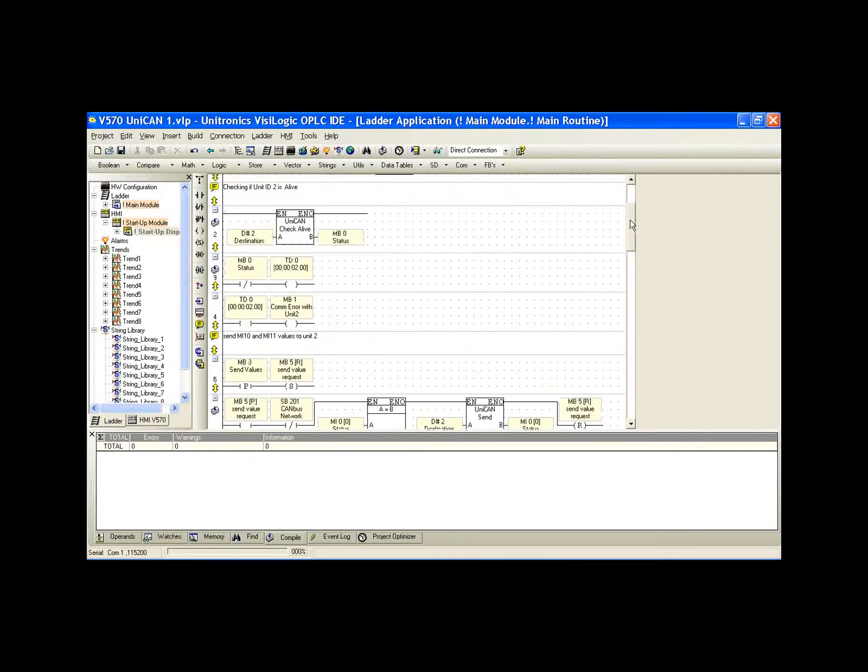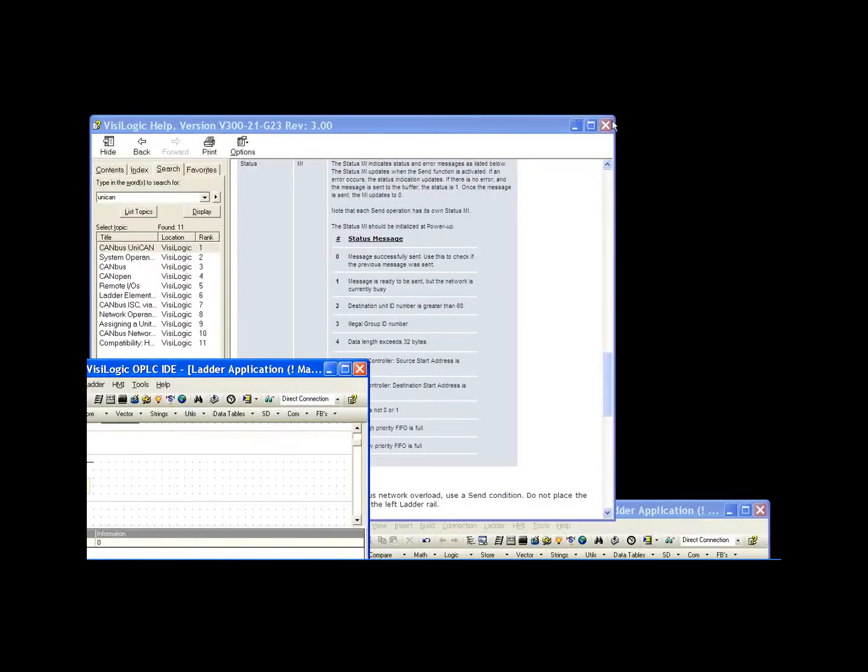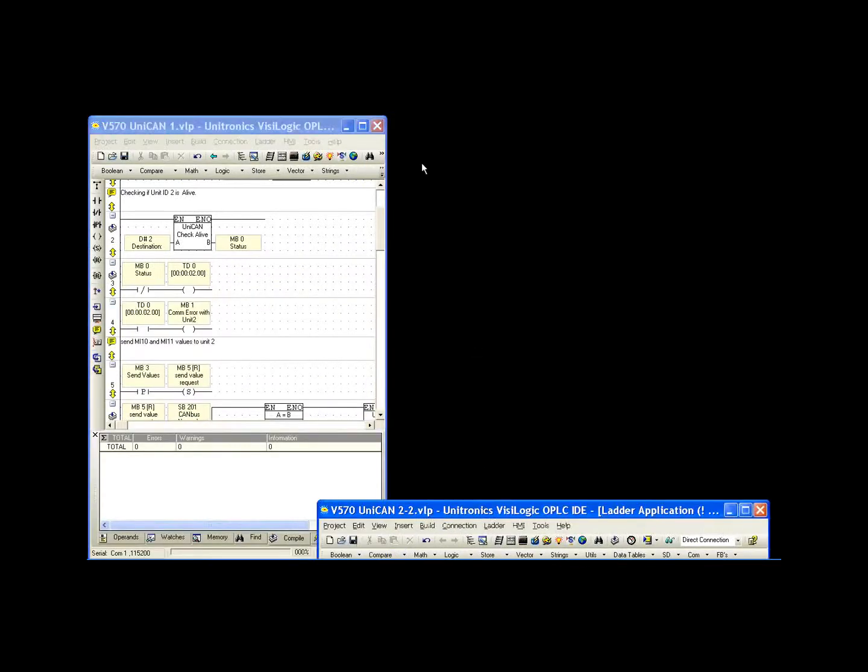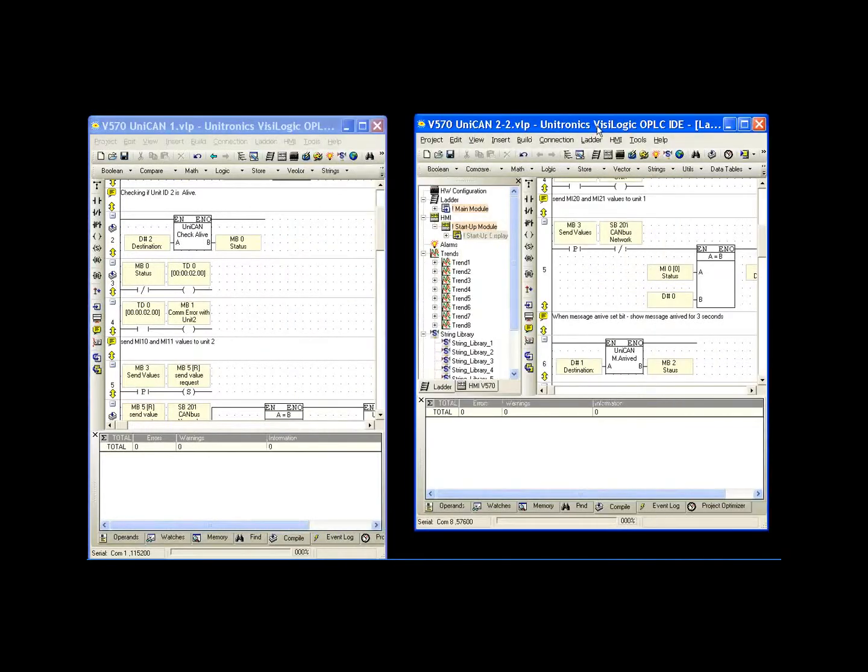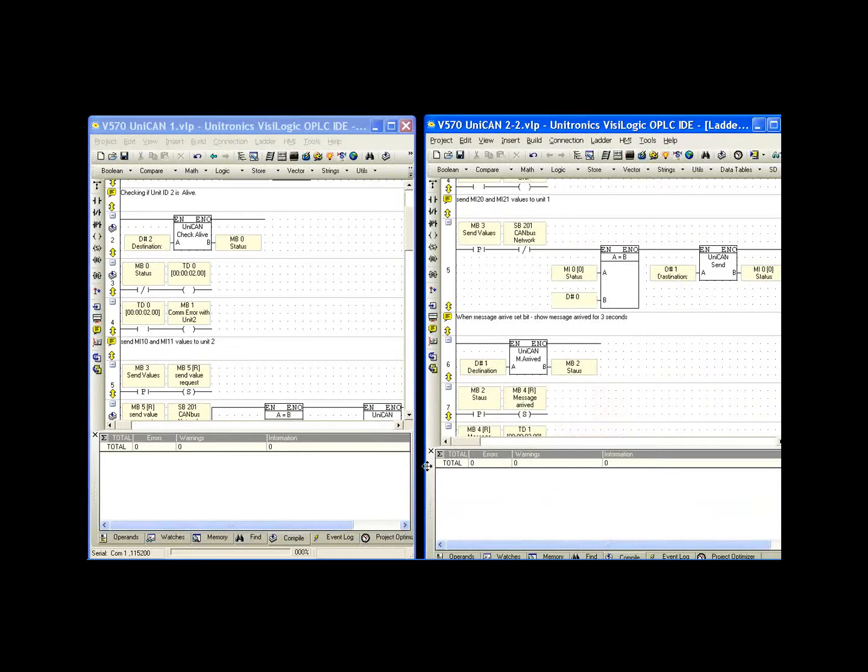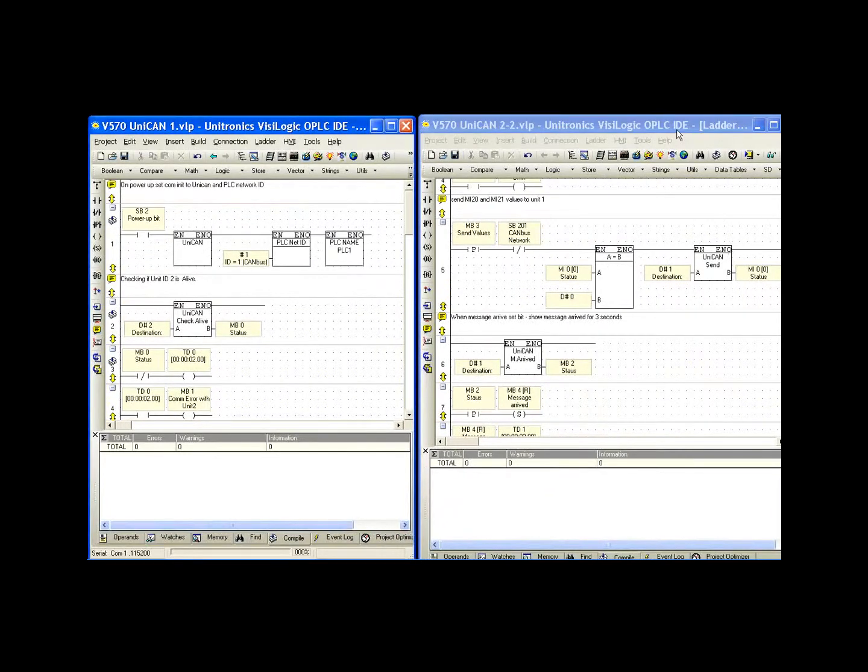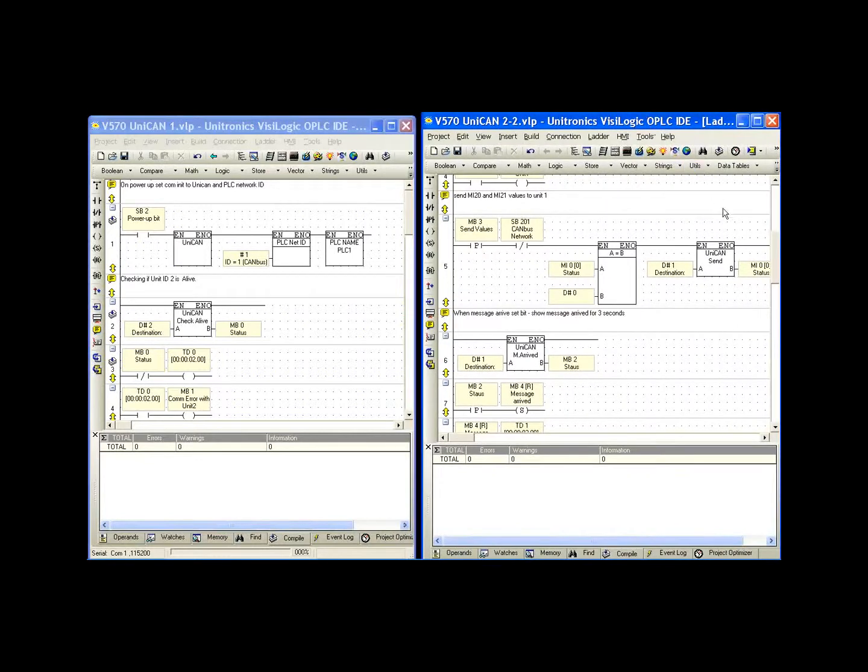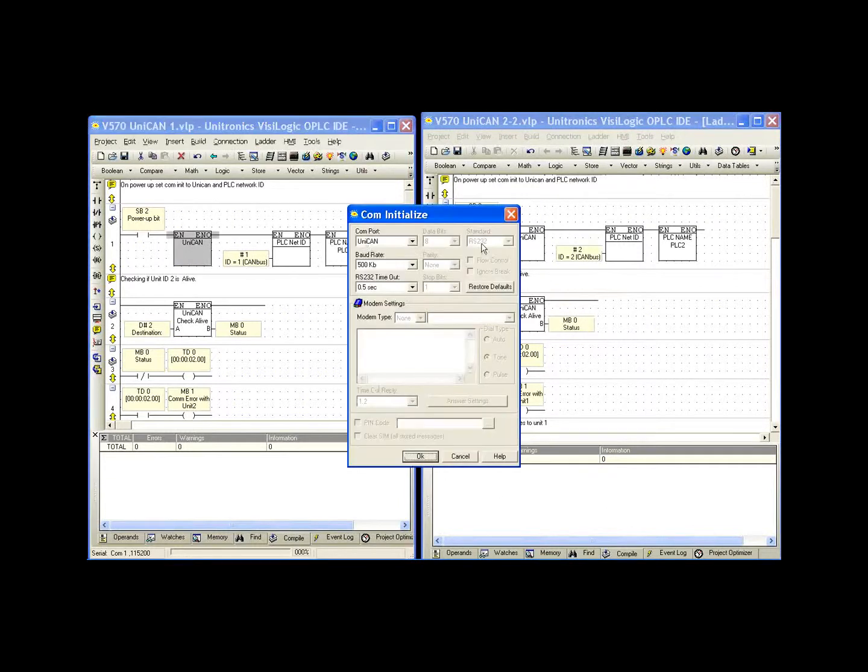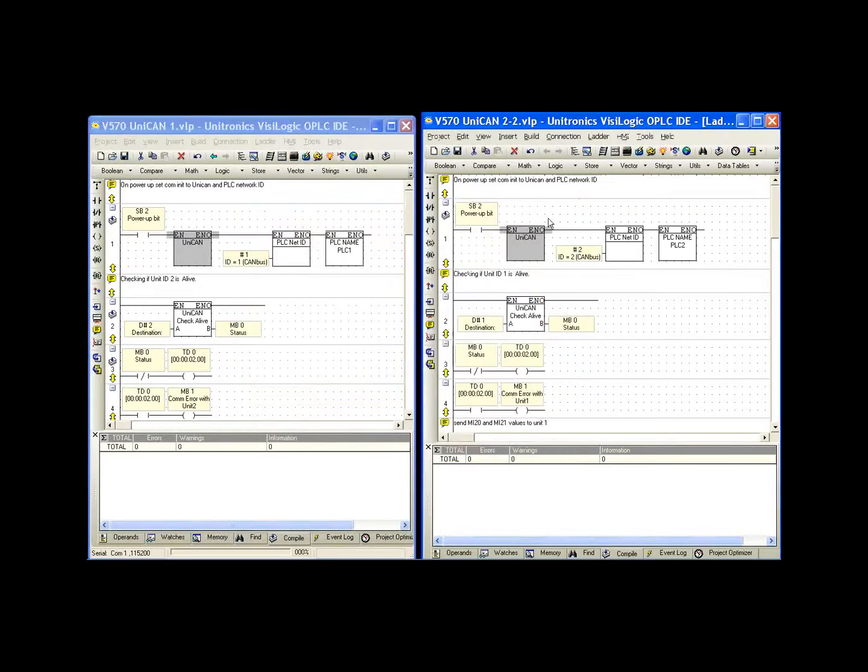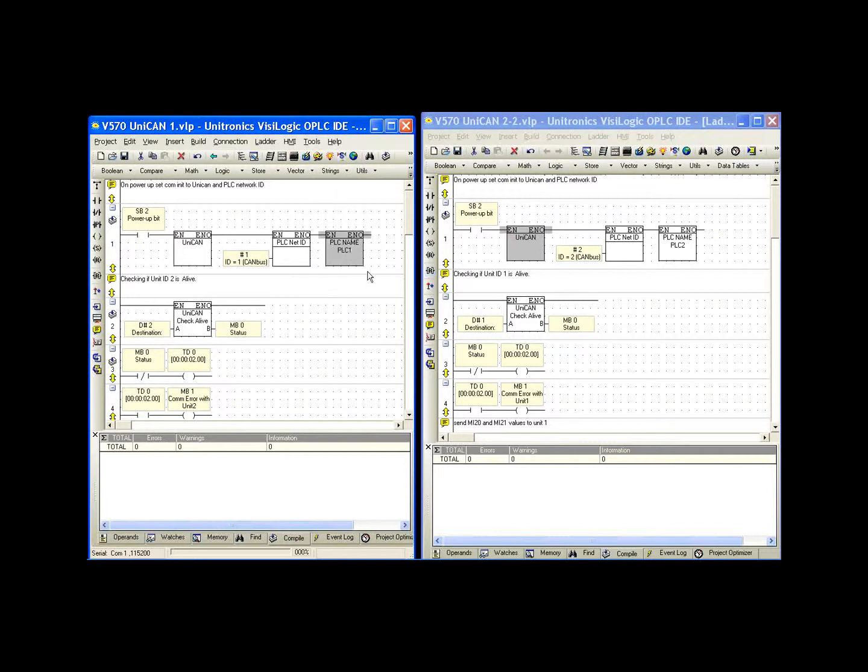We should now take a look at the Unit ID 2 application. Give me a second just to arrange these windows so we can see this in a useful manner. As we noticed from the HMI, the programs are very similar, actually pretty much identical, with the exception of a couple things. What can we expect to be different here? First, of course, is the Unit ID number. In that one of controller 2, again, we have our UNICAN initialization. These need to be the same so we can communicate with each other. That means the baud rate needs to be the same. In program 1, we had ID 1. Program 2, we have ID 2. PLC name for program 1 was PLC name 1. PLC name is PLC 2.